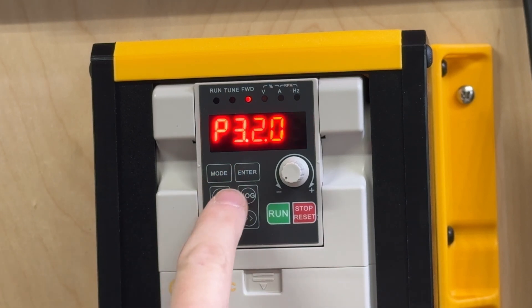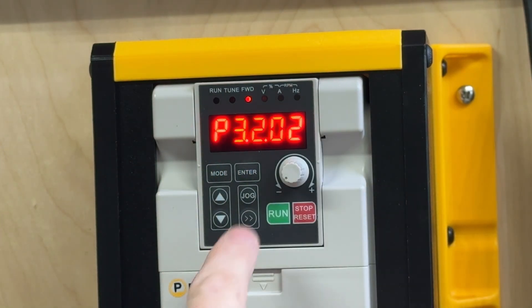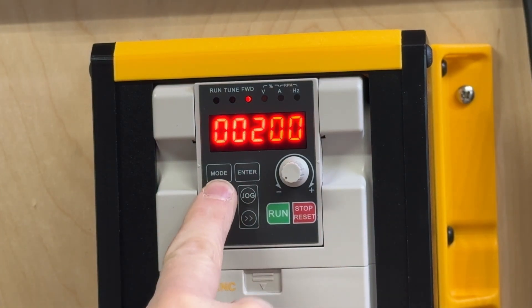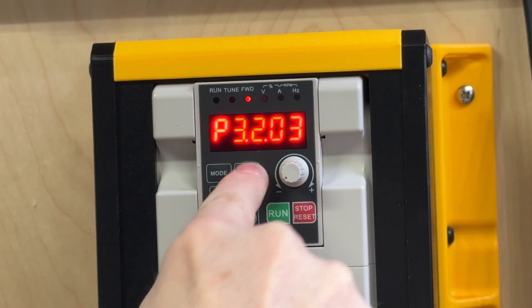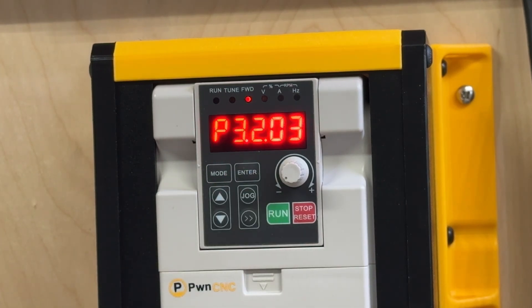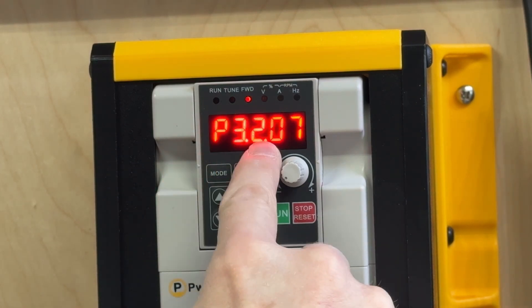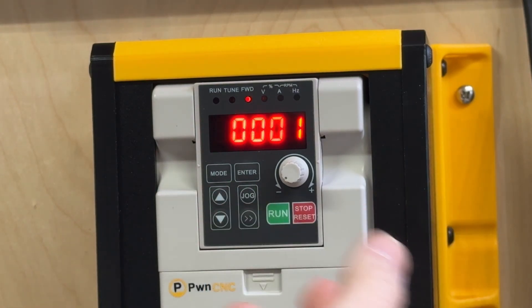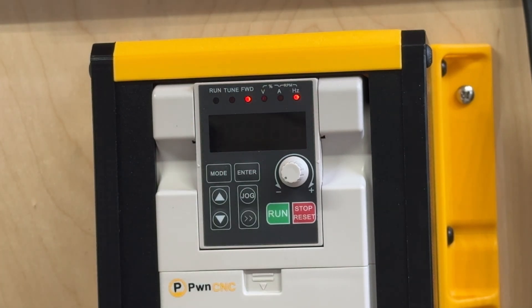The next code: go up one to P3.2.02 and hit enter. We're going to change that to 411 and hit enter. The last code we need to change is P3.2.03 — hit enter, and this one's super easy: just change it to 0001 and hit enter. Now hit mode, and we're done.